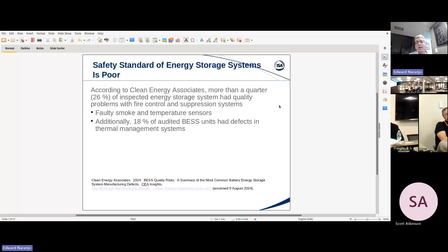According to an industry group called Clean Energy Associates, more than a quarter of inspected energy storage systems had some sort of quality issue, 26% in fact. The most common quality issue was faulty smoke and temperature sensors, and about 20% of audited BESS units had defects in the thermal management system. So this isn't to pick on APS, this was an accident, but the industry as a whole has deficiencies that must be addressed.